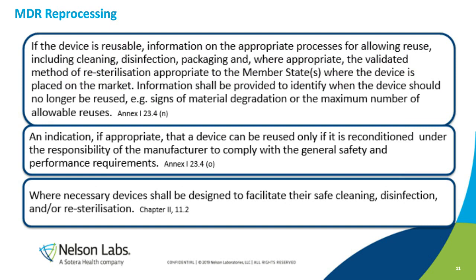Now when we look at the verbiage in the MDR specifically related to processing reusable devices, Annex 1, 23.4, Section N, states that if a device is reusable, information on the appropriate processes for allowing reuse, including cleaning, disinfection, packaging, and where appropriate, the validated method of re-sterilization is appropriate to the member states where the device is placed on the market. Information shall be provided to identify when the device should no longer be reused, for example, signs of material degradation or the maximum number of allowable reuses.